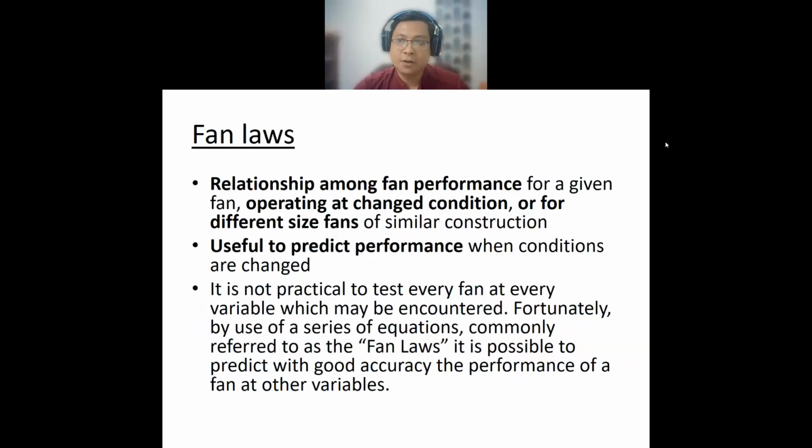Okay, for fan laws, we have here a relationship among fan performance for a given fan operating at changed conditions, or for different size fans of similar construction. This is useful to predict performance when conditions are changed. It's not practical to test every fan at every variable which may be encountered.